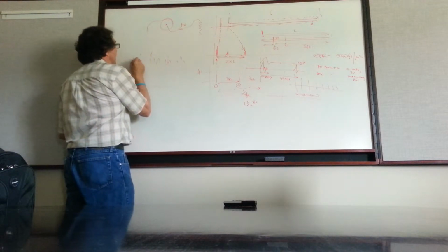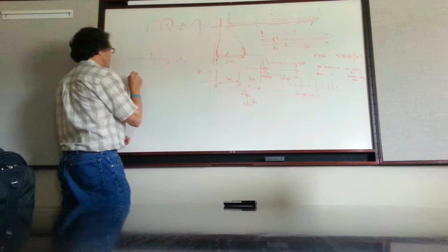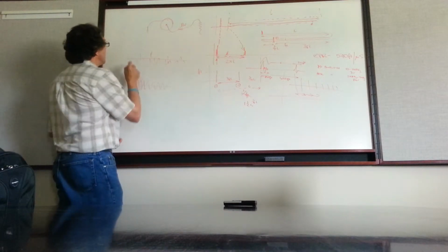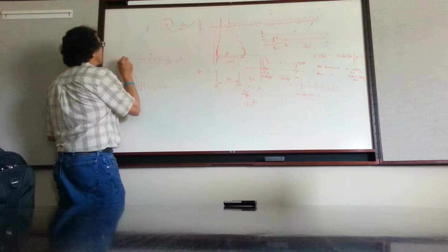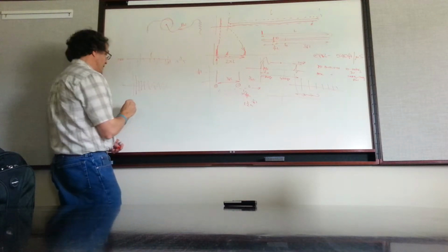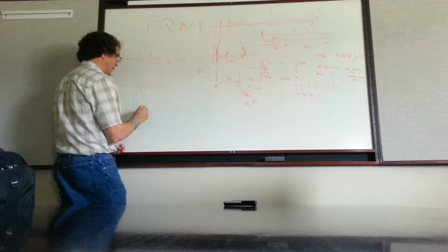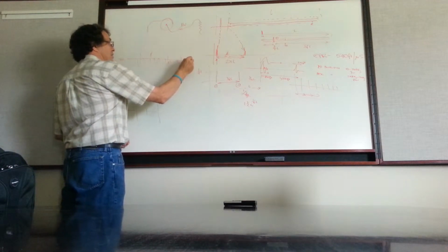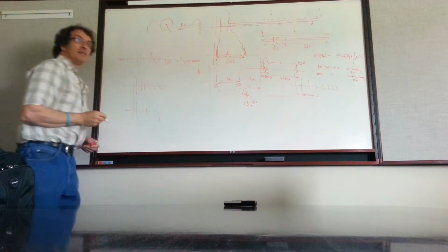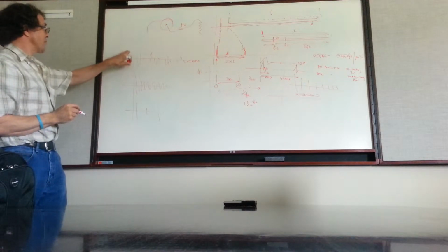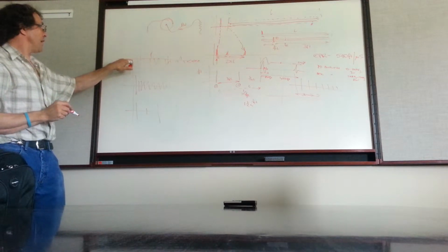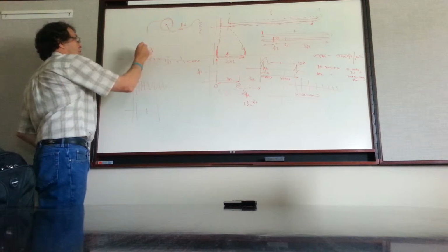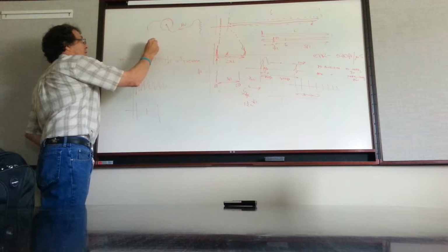So you want to set your gate. Instead of seeing a pulse and then all this lot, where you ask what the hell am I looking at, you set your trigger level to get rid of all this stuff. Then you only see, hopefully, this kind of thing. But that there is your noise level. The higher that noise level becomes, the higher you have to lift your trigger level to get out of the noise, which means the higher the actual fault has to be.